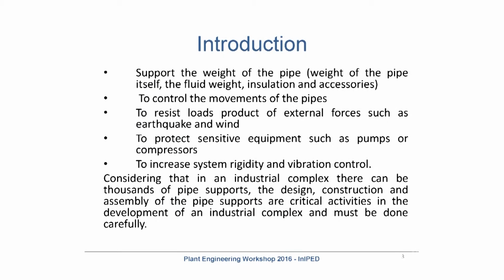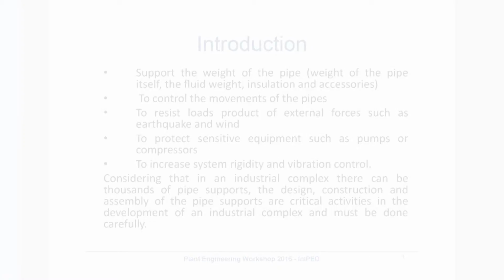So the proper selection of the support is necessary to support the weight of the pipe, of course. When I mean the weight of the pipe, it is the pipe, the fittings, the valves, the insulation, all the elements. It's what we call the weight of the pipe. Also to control the movement, to control the loads that we are going to transmit to the structure and to the equipment, to protect sensitive equipment.